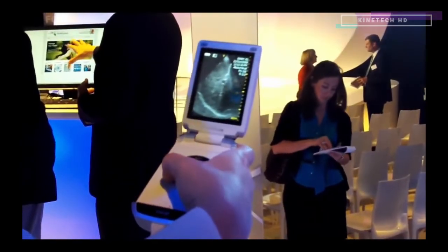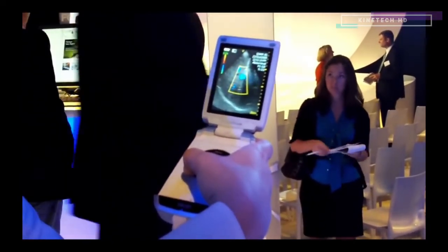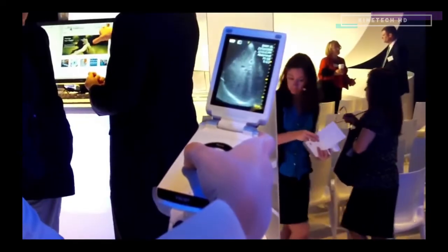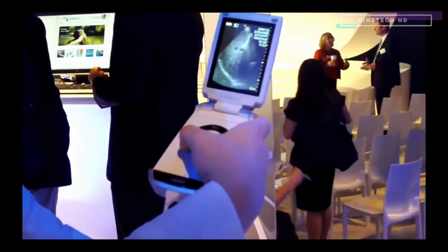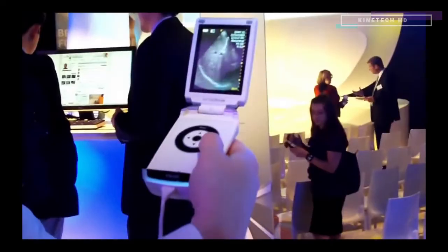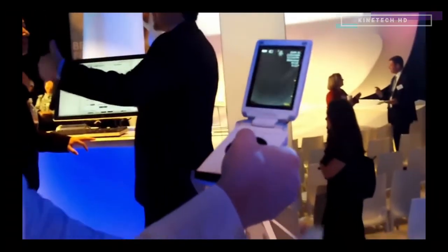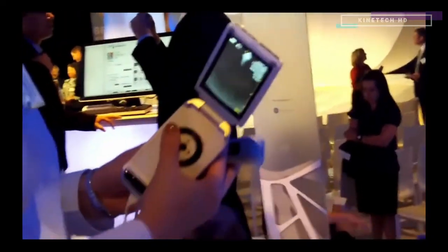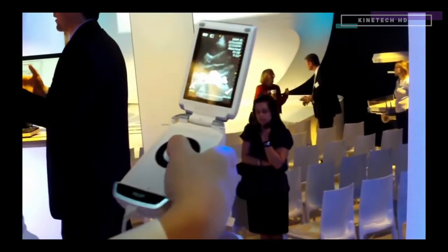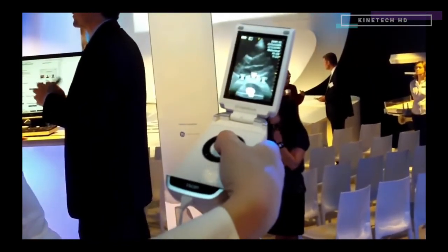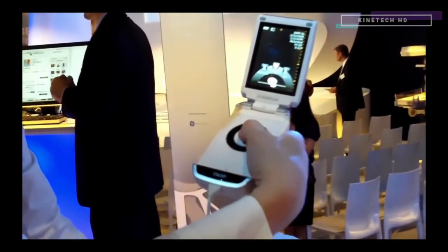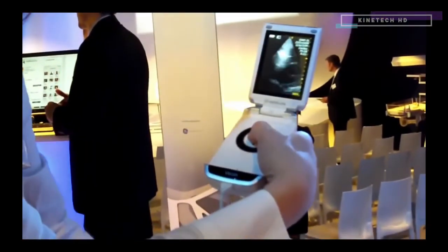We've got color Doppler. Amazing — it's amazing, isn't it? Ten years ago, this thing would have cost like $150,000 to $200,000. That's pretty slick. You do cardiac very well. Just a one-level menu of additional controls, a lot like your personal camera. Just choose a selected preset if needed — that's got a cardiac preset.